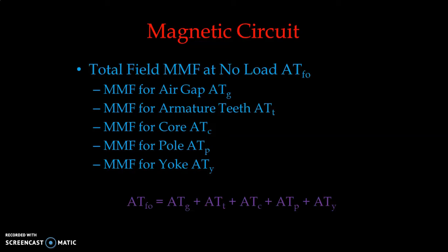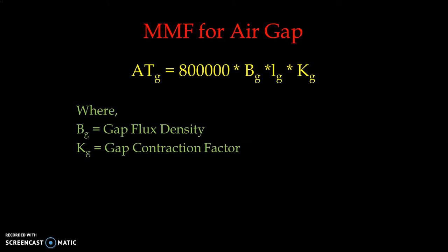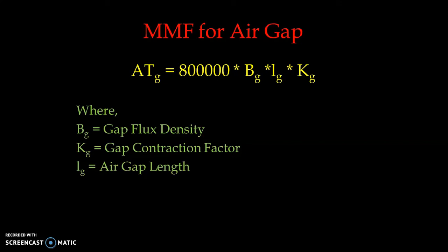We start with the MMF for the air gap, atg. The equation to calculate ampere-turns for the air gap is: atg = 8 × 10⁵ × Bg × lg × Kg, where Bg is the gap flux density, Kg is the gap contraction factor, and lg is the air gap length.